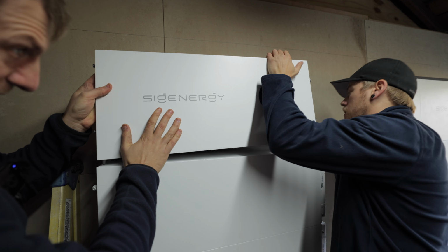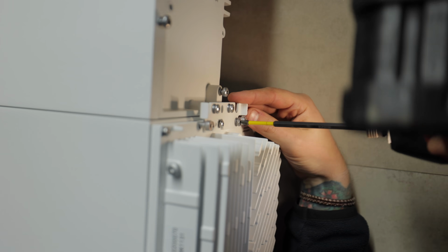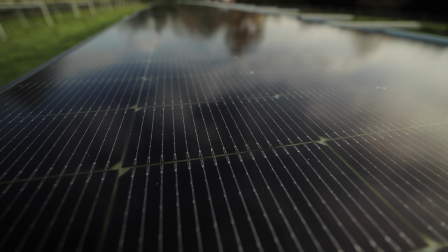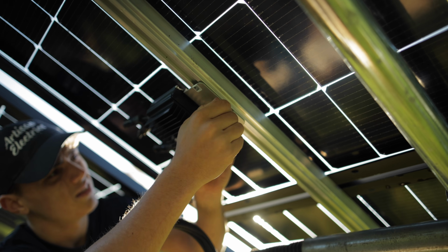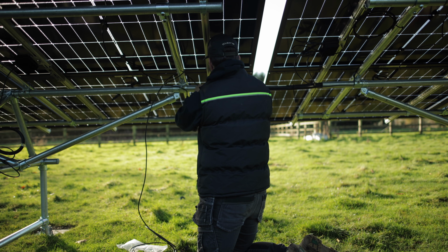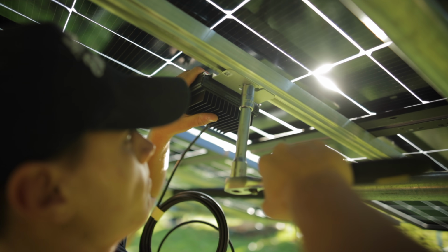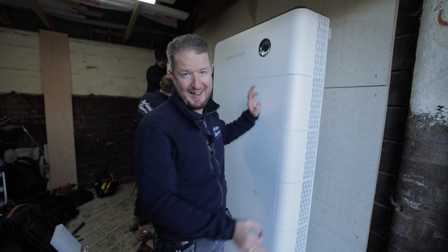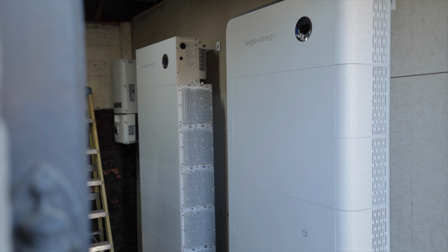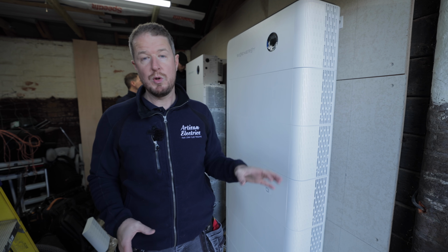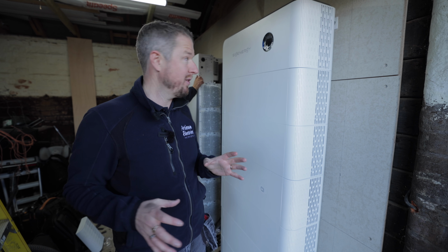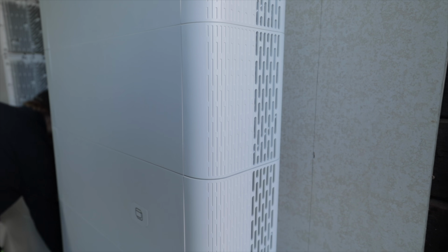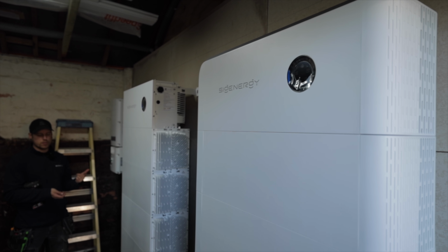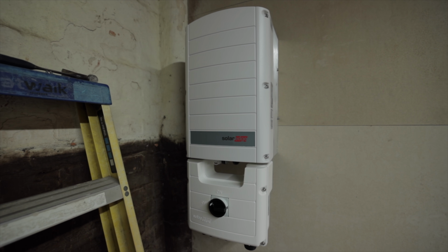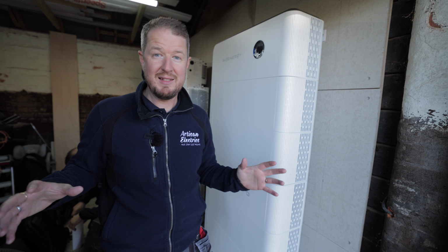While the guys are busy mounting the last of the battery modules, let me give you an overview of this system, it's quite impressive. We've got 120 bifacial 440 watt solar panels, double glass with a transparent backsheet, meaning sunlight passes through them, reflects back off the grass and surrounding area, giving extra generation. But these are really the highlight for me: 2 stacks of Sigenergy 8 kilowatt hour battery modules, for a total of a whopping 88 kilowatt hours of battery storage. We've also got this, completely new for us, which we'll cover in depth in a separate video - a bi-directional DC EV charger module that stacks within these batteries. We've got a total of 30 kilowatts of battery inverters and a 30 kilowatt SolarEdge inverter, and the whole system is going to basically take the customer completely off grid.